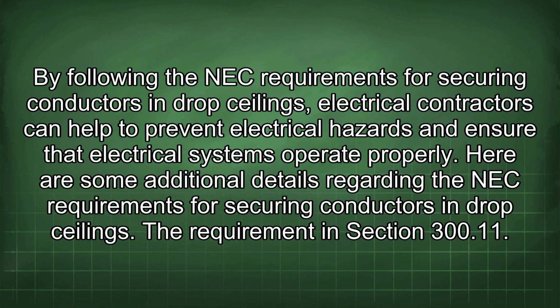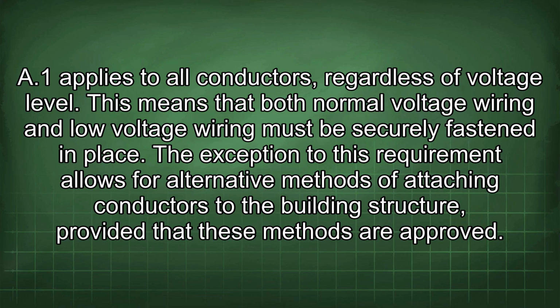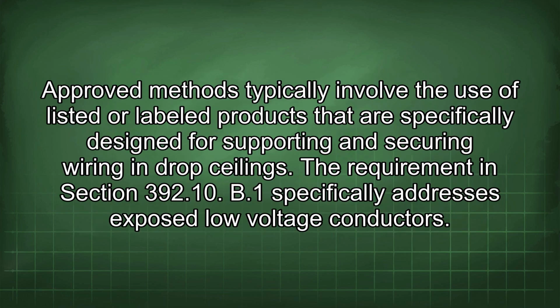Here are some additional details regarding the NEC requirements for securing conductors in drop ceilings. The requirement in section 300.11 A1 applies to all conductors regardless of voltage level. This means that both normal voltage wiring and low voltage wiring must be securely fastened in place. The exception to this requirement allows for alternative methods of attaching conductors to the building structure, provided that these methods are approved. Approved methods typically involve the use of listed or labeled products that are specifically designed for supporting and securing wiring in drop ceilings.